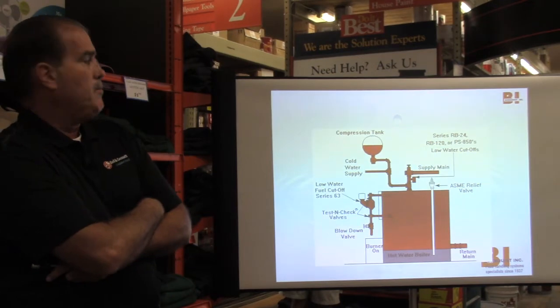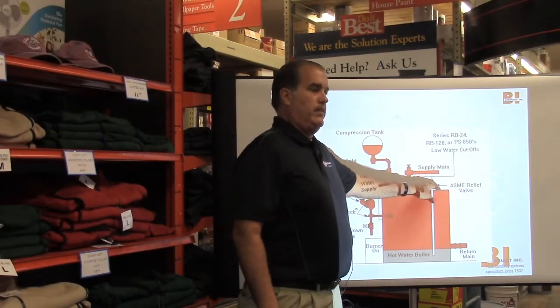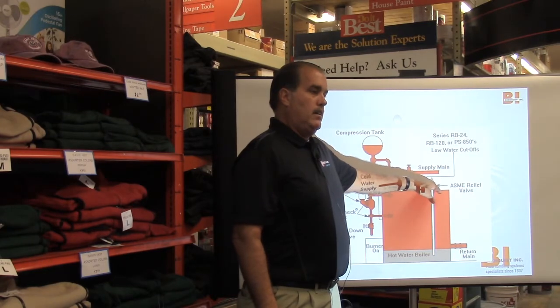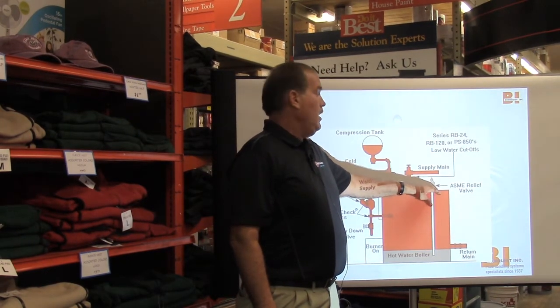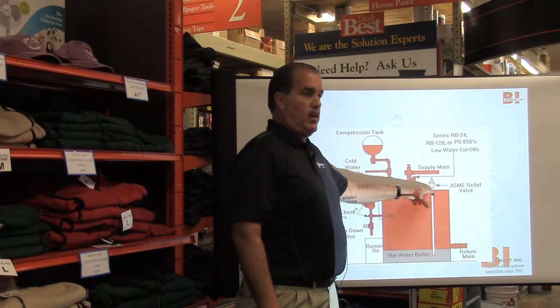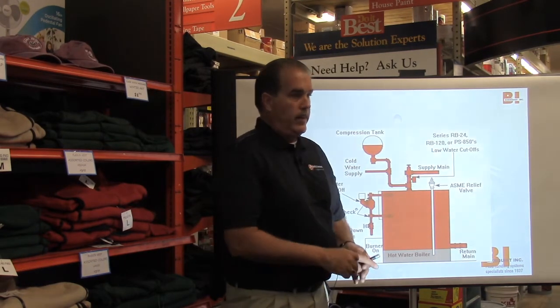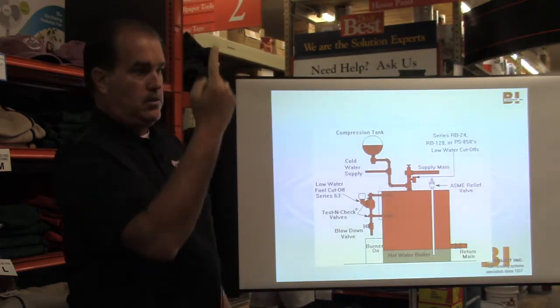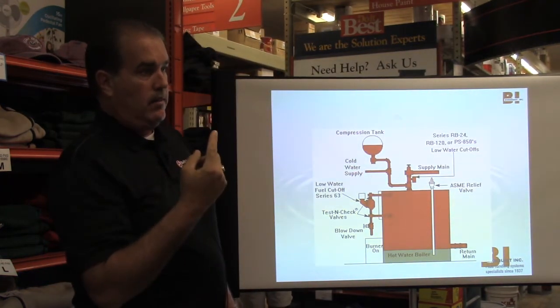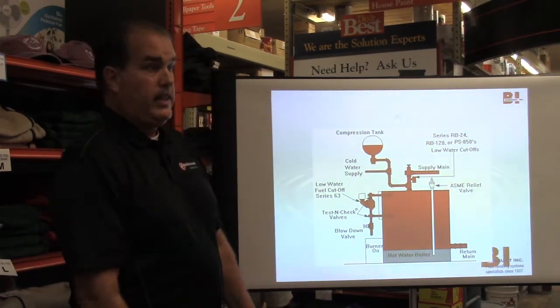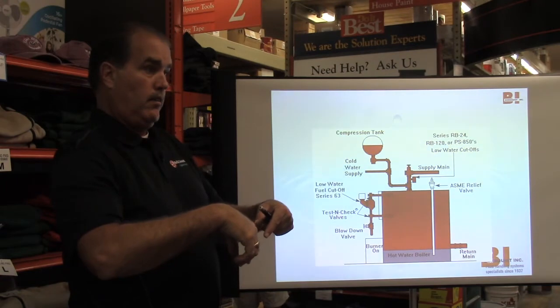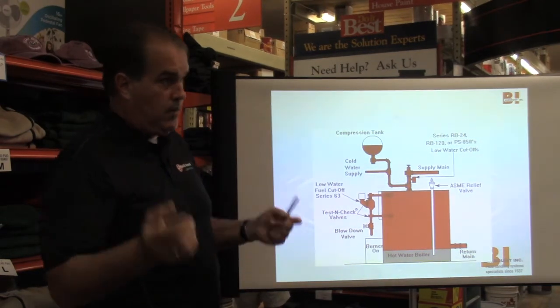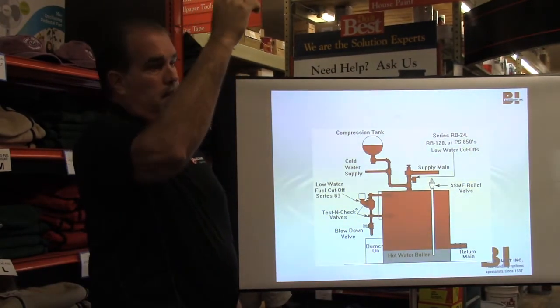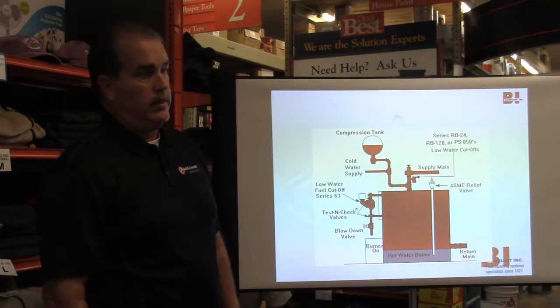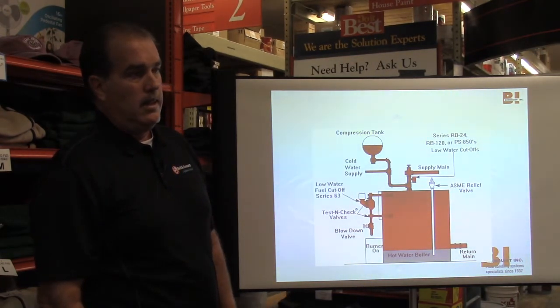See, this is the same problem, and it's with the relief valve. It's the same issue: debris. When this valve opens and closes, debris gets caught between the seat, and it sometimes can leak. That air vent has a little float in it, and there's a little needle and pin that goes up and down. When it drops down, because the water's leaving, it's letting the air in while it's draining. When you're filling, it's doing the same thing, letting the air out until it gets to that point, and then the float seals up against the seat. If there's any debris, you can get a leak, and it can get a little trickle.